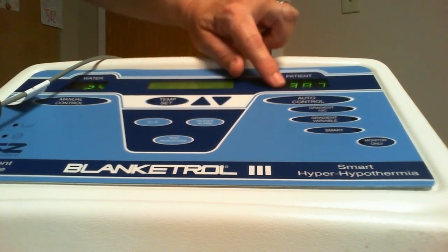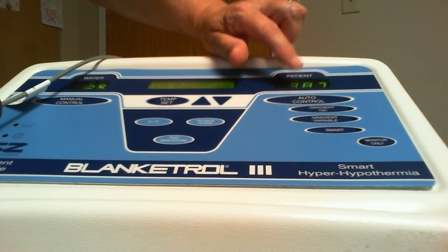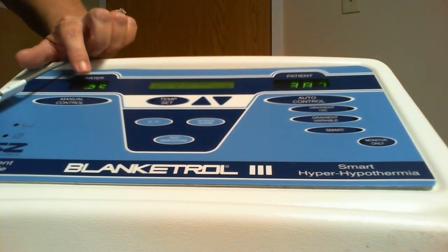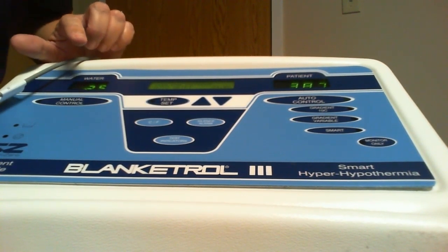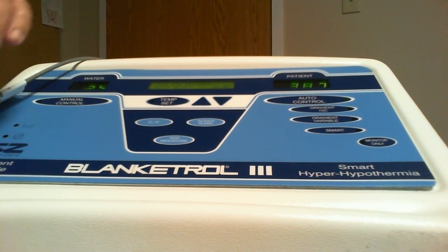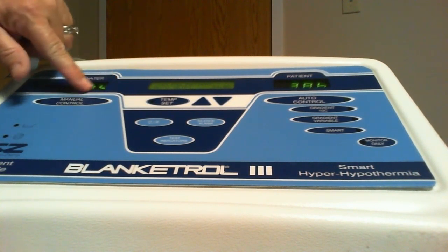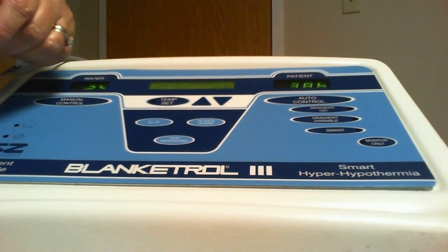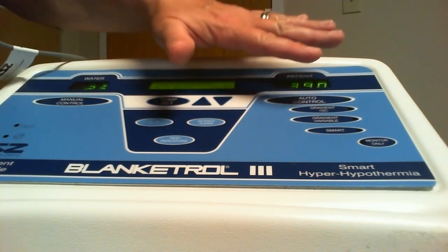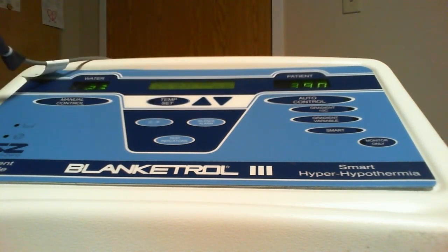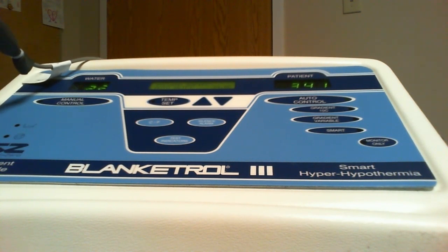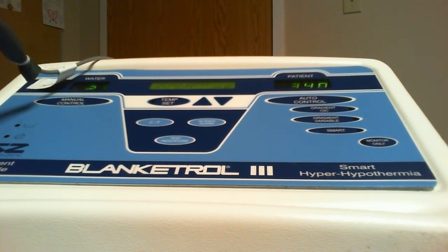it comes up and it tells me my patient temperature right here is 38.7. My water temperature is 25. Water is going to start circulating through both of the blankets. And this water temperature can go down as low as 4 degrees. In the auto mode, the philosophy is get the patient down as quickly as possible. And so water is filling the blankets, and I'm simulating my patient's temperature dropping. It wouldn't drop immediately, but our plan is to get to target temperature within 4 hours.